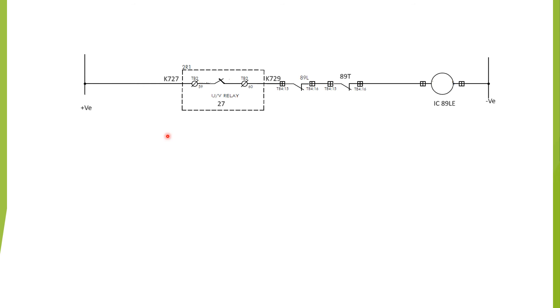In this diagram the interlocking coil for the line earthing switch has been shown. There exist three NC contacts: one is the under-voltage relay NC contact (27), another is the 89L line isolator NC contact, and another is the 89T transfer bus side isolator NC contact. If all three conditions are fulfilled, only then will the interlocking coil be energized and we can operate the line earthing switch electrically.